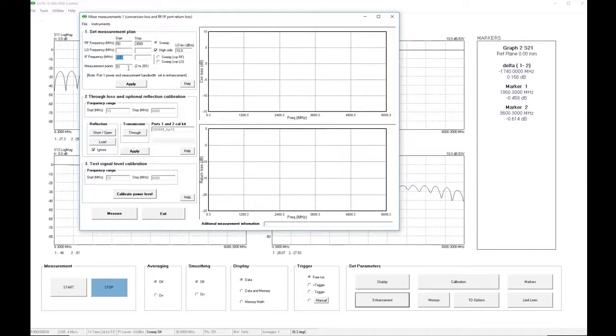Next thing, we tell the software what IF frequency we want, and I'm going to use 30 MHz. Here at the bottom, we have the number of measurement points, and I've written 51 in there, which is a reasonable number for this demonstration. Finally here, in the top right box, we can put in the level that we want for the local signal generator. This mixer is rated at 10 dBm, so that's what we're going to use here. Now we're ready to apply, and those values are now set.